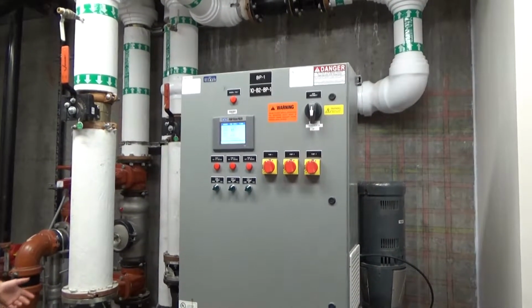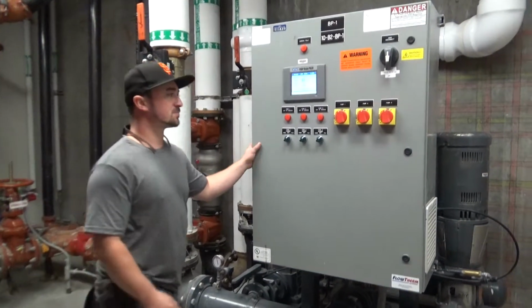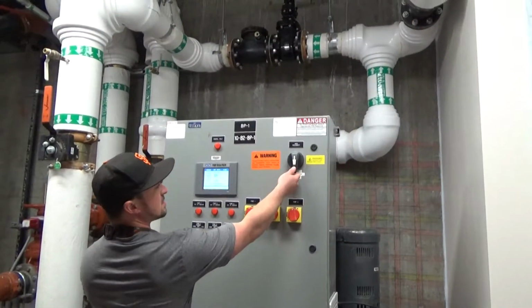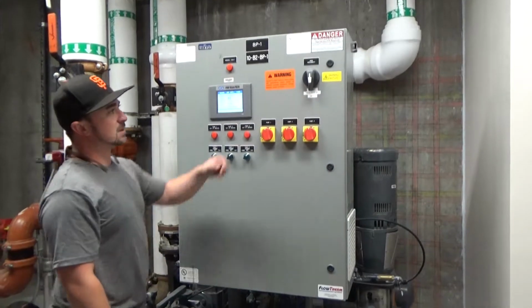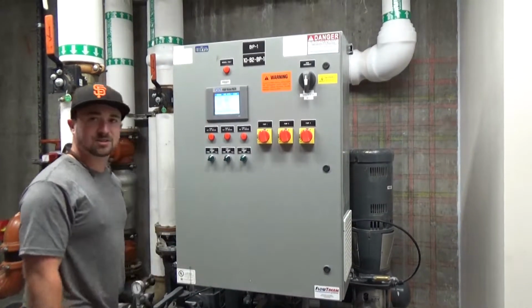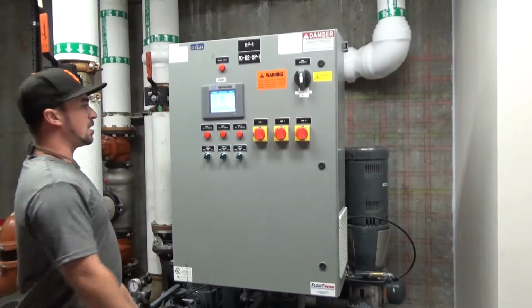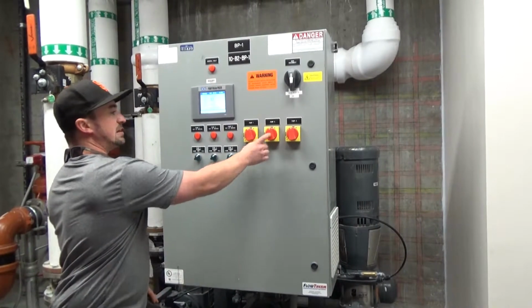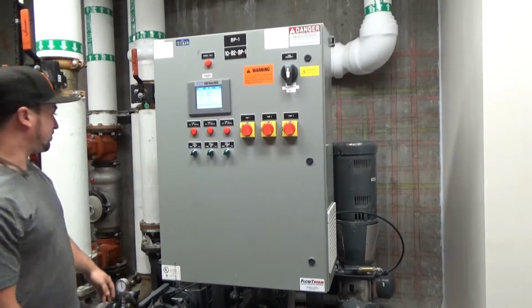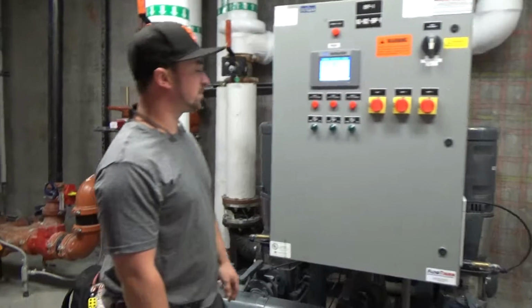So right off the bat, you have your main control panel. The main control panel has its main disconnect right here. You flip that main disconnect, it's going to kill power to everything down below. Right here you have your overloads for each individual pump. So if that motor starts drawing too much amps for whatever reason, the overload's going to trip.